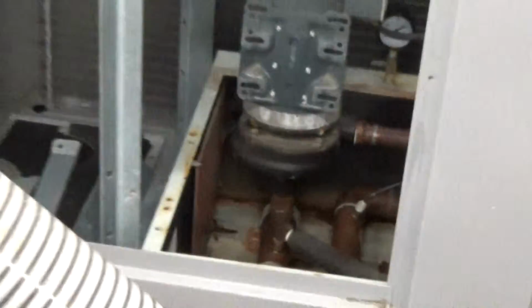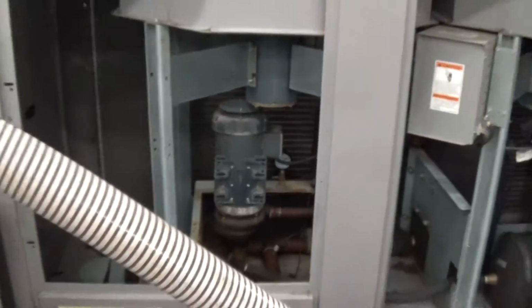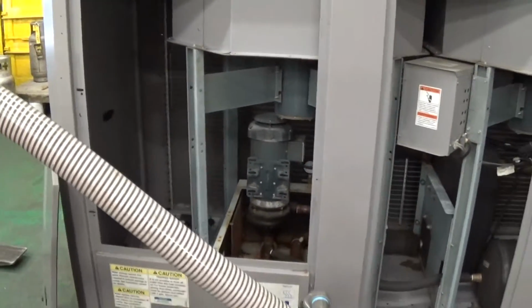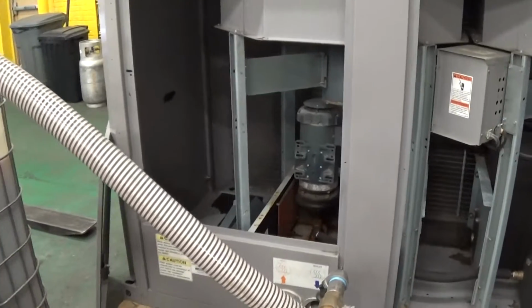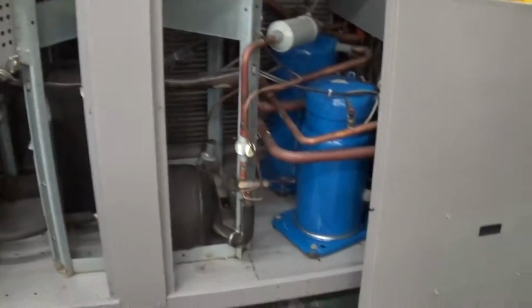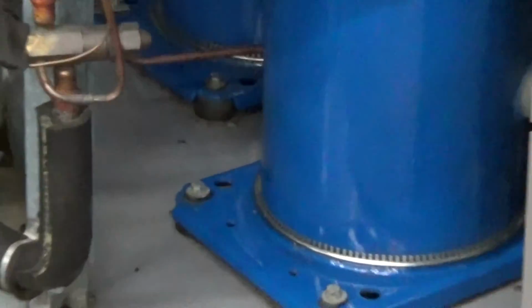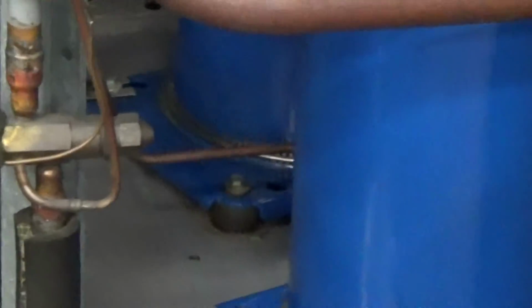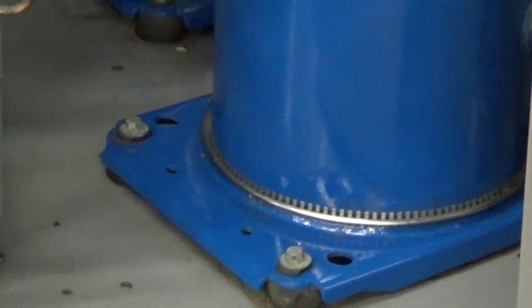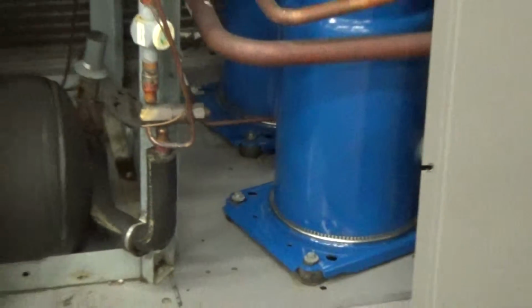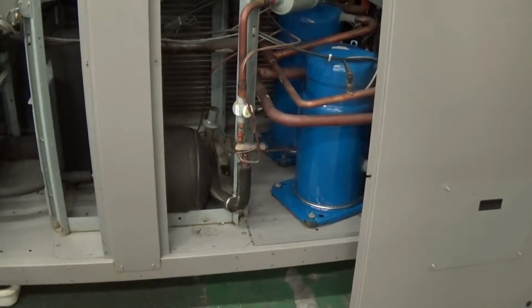If you see a little maroon section there, that red, that's actually a heater. So that area inside is actually heated to avoid any freeze-ups. Probably not a problem anyway if you use proper glycol mix, but it's nice to know. In addition to that, both compressors have heater bands on them. So as long as you have power to the unit, those heater bands will be on, which is good for cold weather starting and stopping.